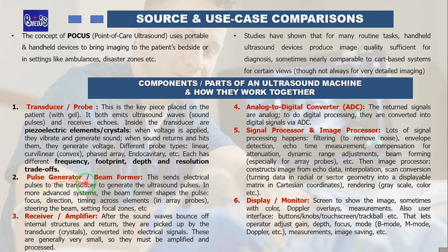Then the next thing is the pulse generator or beam former. This sends electrical pulses to the transducer to generate the ultrasound pulses. In more advanced systems, the beam former shapes the pulse, focus, direction, timing across elements in array probes, steering the probes, setting focal zones, etc. Now we also have the receiver or amplifier. After the sound waves bounce off internal structures and return, they are picked up by the transducer crystals, converted into electrical signals. These are generally very small or very weak, so they must be amplified and processed.